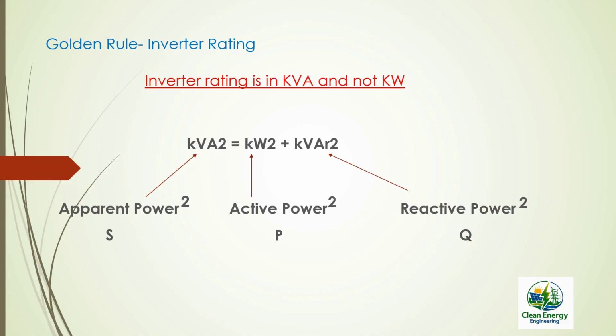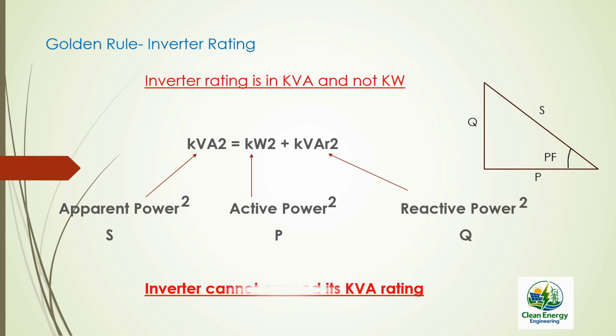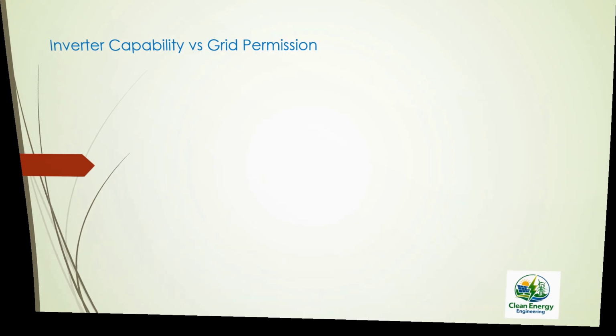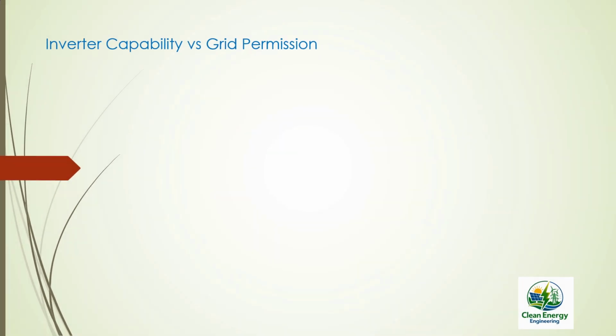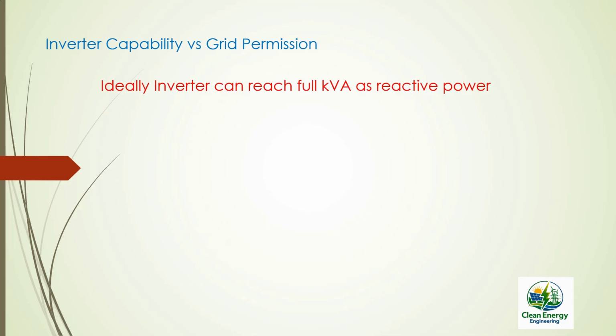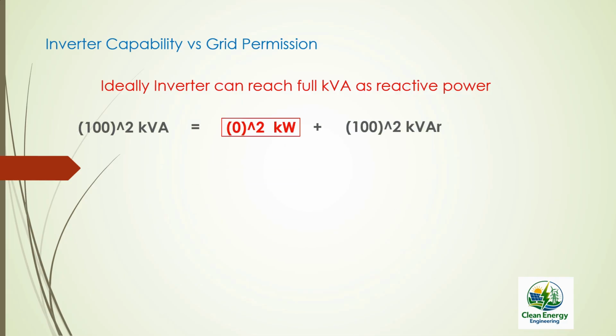So active power is actual energy, reactive power supports voltage and system stability. Apparent power is total inverter capacity in kVA. So reactive power is not extra capacity, it comes from the same inverter limit. Ideally, an inverter can convert the entire kVA into reactive power when there is no active power. So a 100 kVA inverter can generate 100 kVAr of reactive power when active power is 0. But in the real world, most grids allow operation between 0.8 lagging to 0.8 leading power factor.